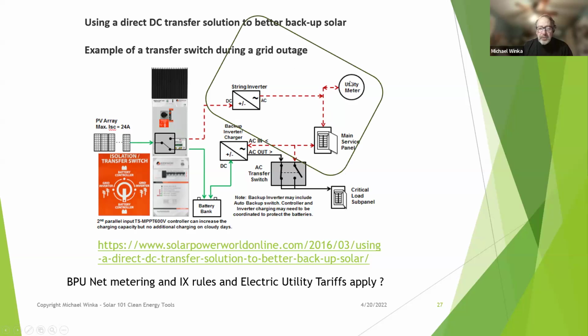If the grid goes down, all of this shuts down. The inverter shuts down this piece. It senses the grid is out. With this transfer switch, it automatically transfers that power over to this critical load subpanel. It still takes power from your solar panels, charges it into the battery, and the battery sends out AC load to your house. Whatever's on this critical load panel gets to run, but you're not running in parallel with the grid—you're isolated, in what's called island mode. When the grid comes back up, that goes away, and you're running back on the typical system with the string inverters. So you can do that right now with vehicle to load, or solar panels to load.